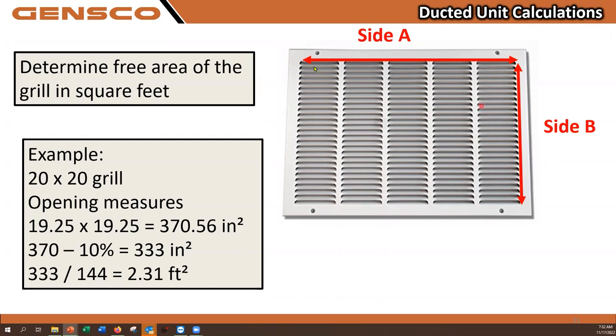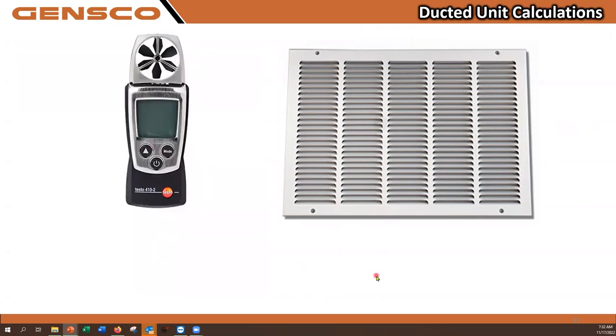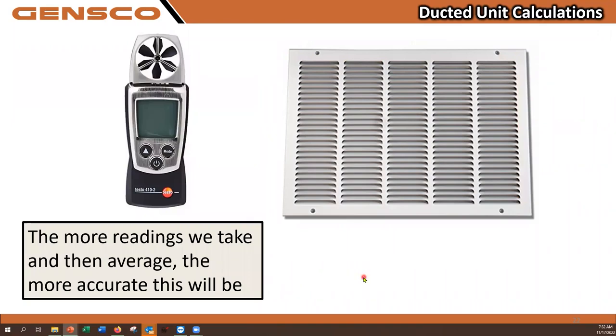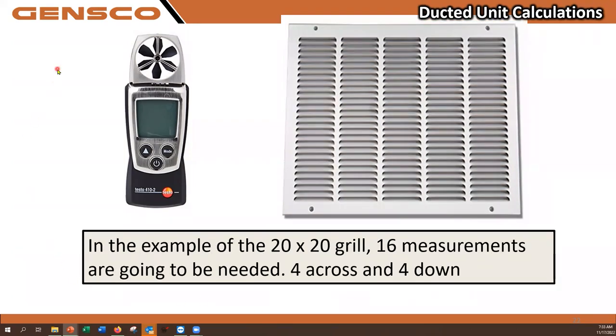So after I have determined the area of my grill, the free area, next I'm going to need something that can measure velocity. In this case, an air vane velometer. And with a grill that's 20 by 20, I'm going to take a bunch of readings across this grill and get an average of the air that's going through the grill. The geometry of what's behind this grill can cause the velocities to be drastically different in different parts of the grill, depending on what kind of ductwork, where the ductwork takes off. All those things come into play. This is why you need as many measurements as you can to get an accurate number. In the case of a 20 by 20 grill, I'm going to take 16 measurements, 4 across and 4 down.